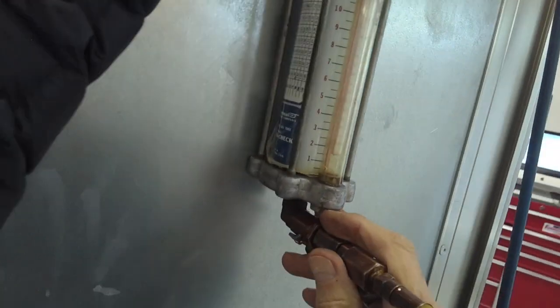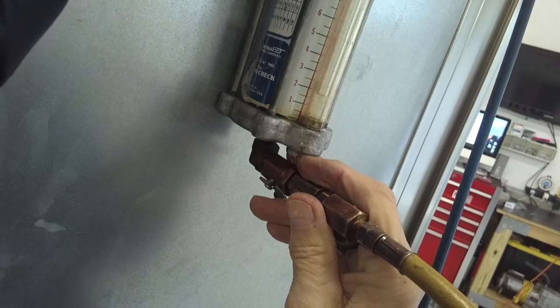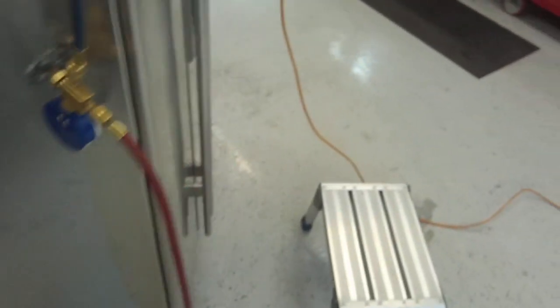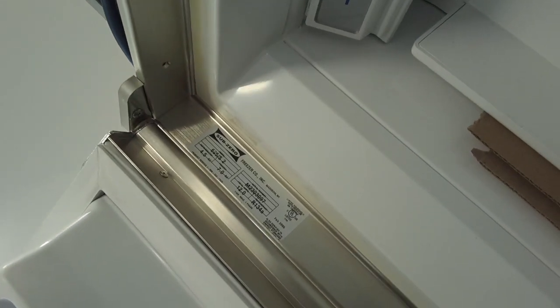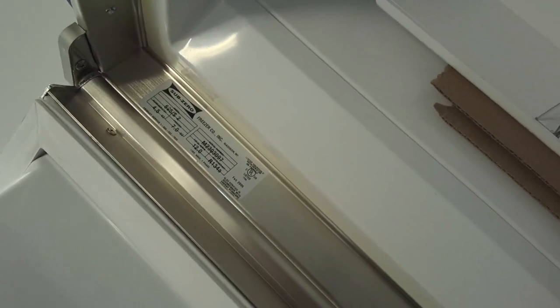We pulled out, it looks like 2 ounces of gas. 2 ounces of gas is low. Let's see what this thing takes. The refrigerator takes 7 ounces of freon 134A. So it's low, that's for sure. Alright, so let's work on the dryer.